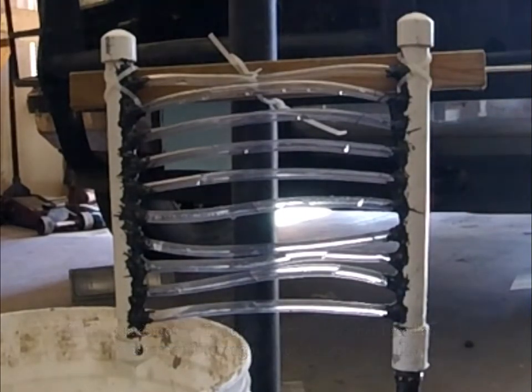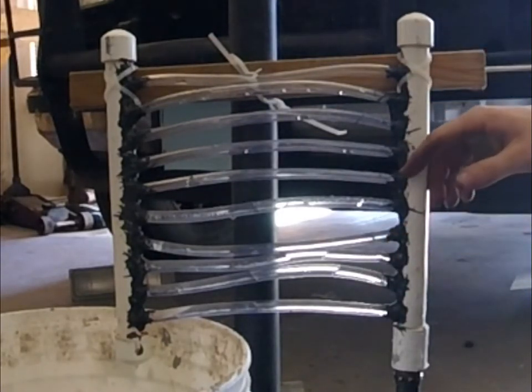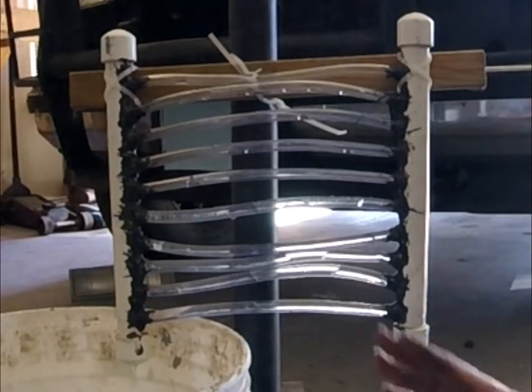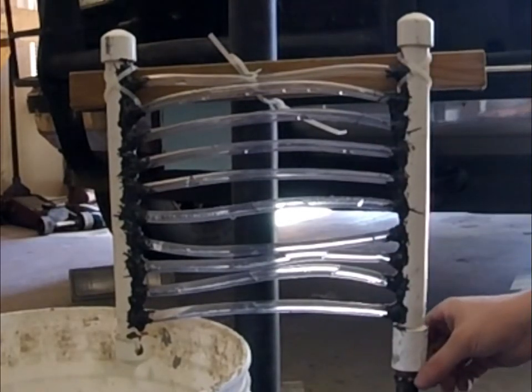The problem with this is it airlocks part of the system, which we'll get to in a second. But the reason most coolers are mounted this way is because it's a lot easier - the transmission lines just come up and then they hook right up to the cooler.